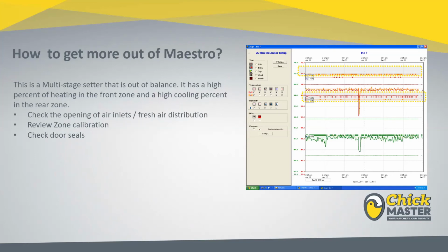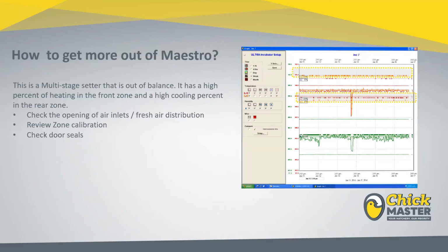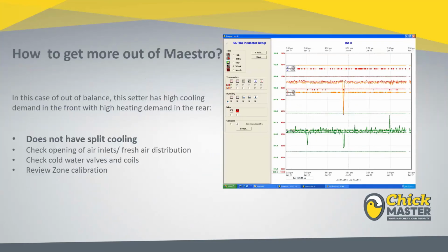So this can be an indicator of an out of balance fresh air distribution. It can also indicate that maybe the temperature probes need to be calibrated, or oftentimes you have a door seal on the front of the machine that's letting a lot of cool air migrate into that front zone and causing that excessive heating in the front. And that may be causing overheating in the rear and causing it to have to cool. So there's a lot of little details around this that can be dug into with multi-stage.